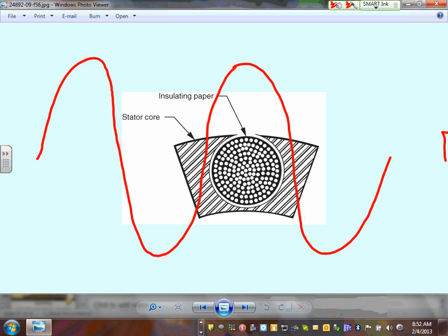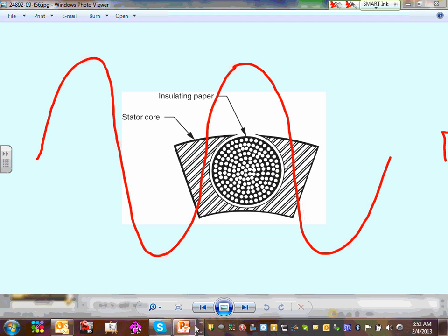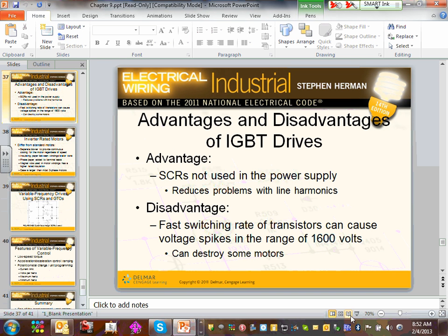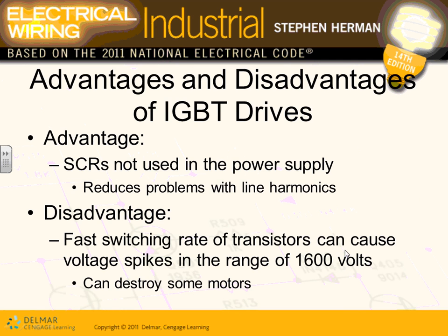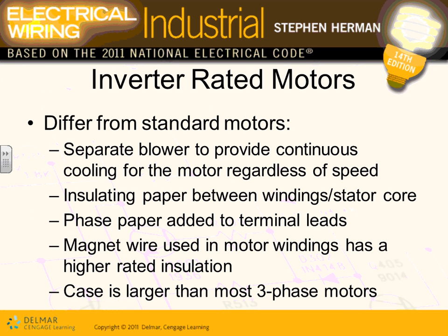The last thing, guys, in my thing here to do is almost done here. So we talked about IGBTs. Then, you guys remember that signal, the pulsation signal? This is so harsh on the motors, so harsh. It creates a lot of heat in the motors. So the manufacturers of the motors started creating something called inverter-rated motors.